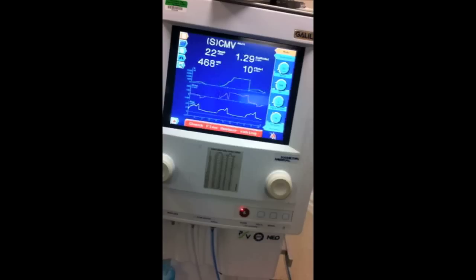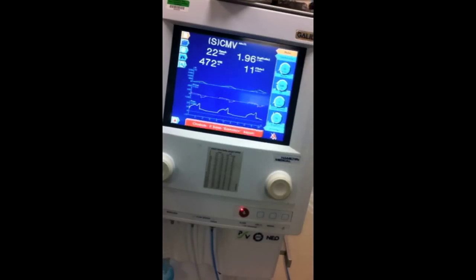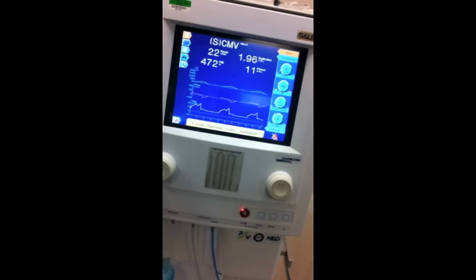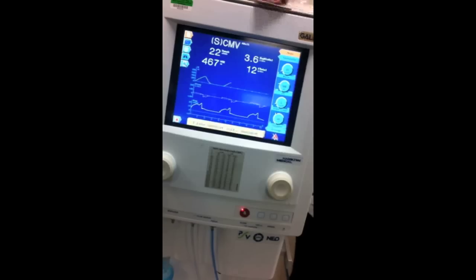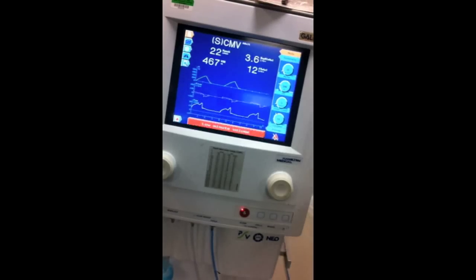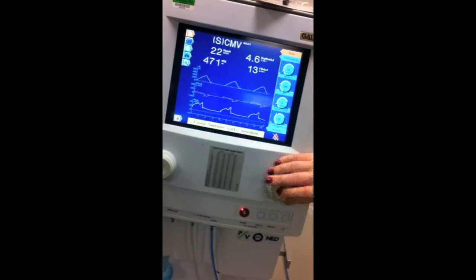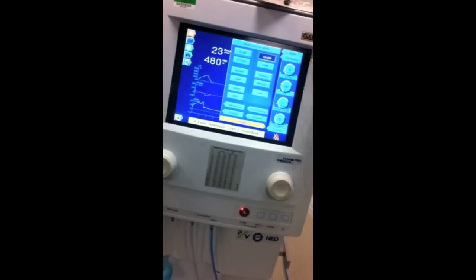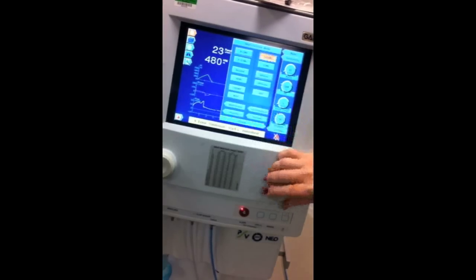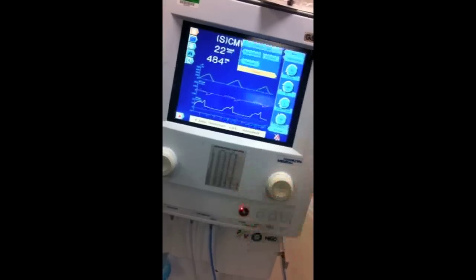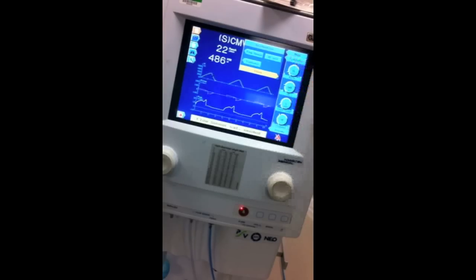Part of this calibration is doing a flow sensor test and a tightness test. To get to that section, this is usually hanging by one of those little ring things on the back of the ventilator. To get to the calibrations, you go to the mode screen, and then you scroll down to calibration. Right there. When it says orange, remember, hit the button to confirm. It will take us over to that screen. We have the flow sensor test and the tightness test. We do not do an O2 cell test unless the ventilator tells us we have to.